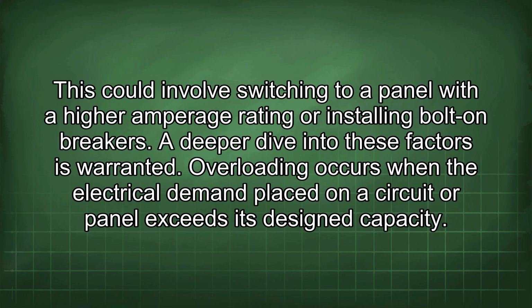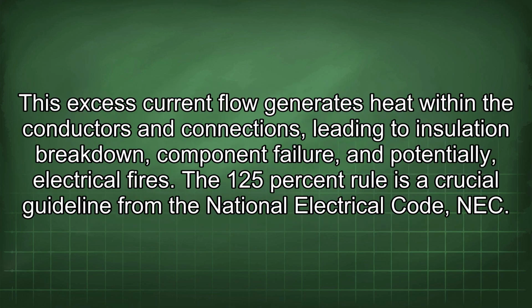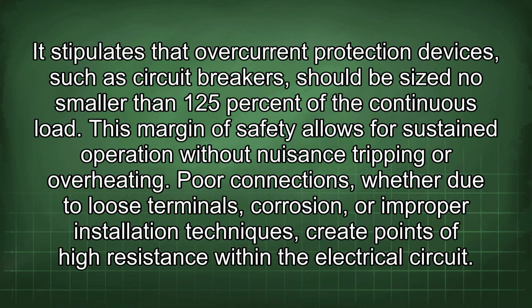Overloading occurs when the electrical demand placed on a circuit or panel exceeds its designed capacity. This excess current flow generates heat within the conductors and connections, leading to insulation breakdown, component failure, and potentially electrical fires. The 125% rule is a crucial guideline from the National Electrical Code, NEC. It stipulates that overcurrent protection devices, such as circuit breakers, should be sized no smaller than 125% of the continuous load. This margin of safety allows for sustained operation without nuisance tripping or overheating.